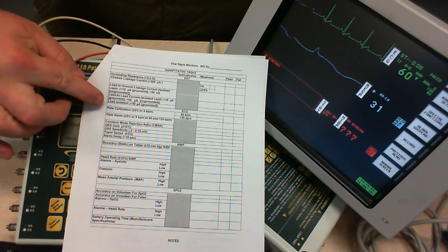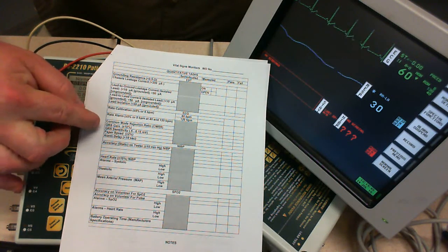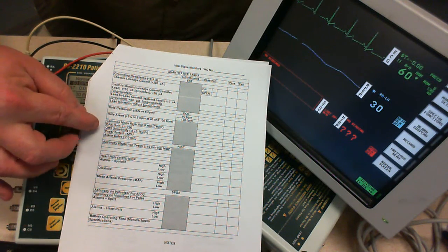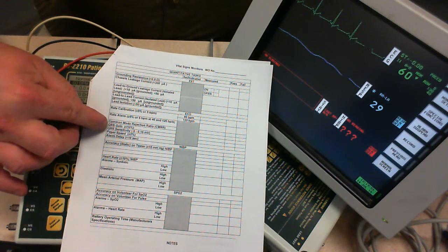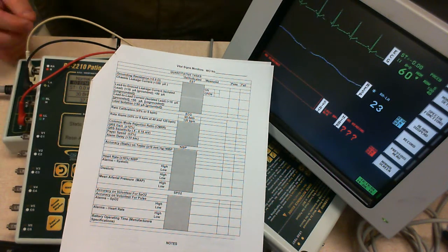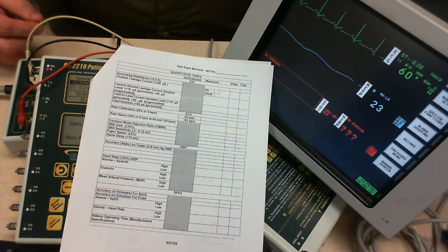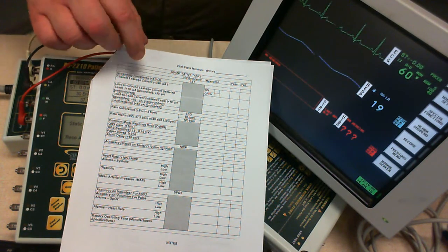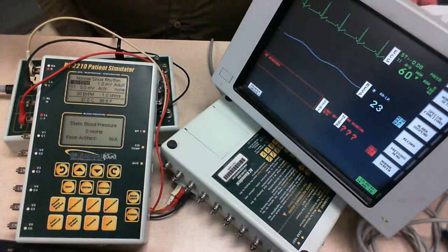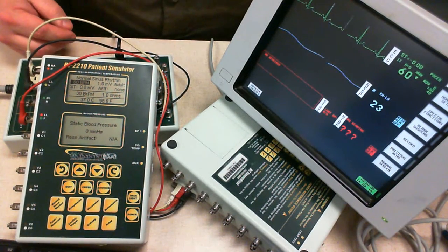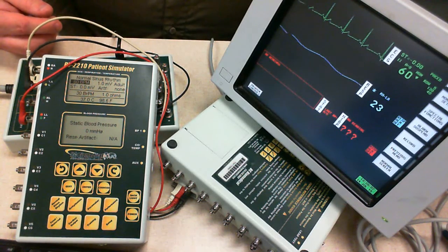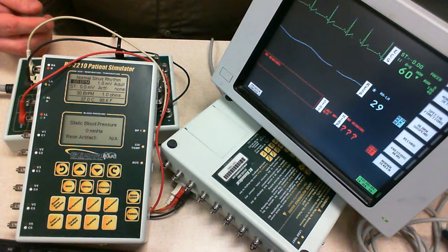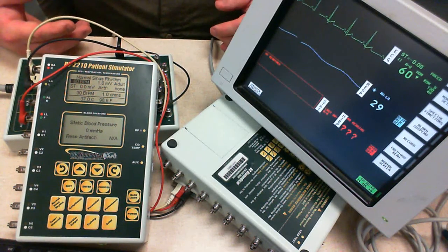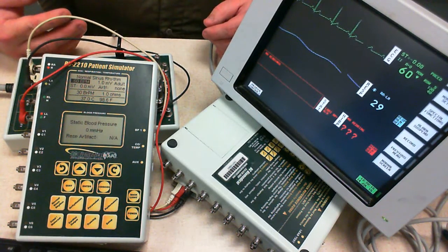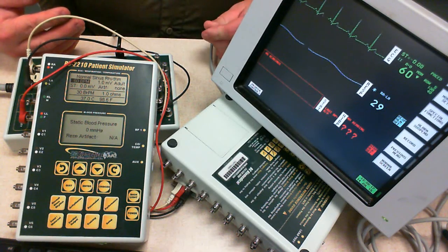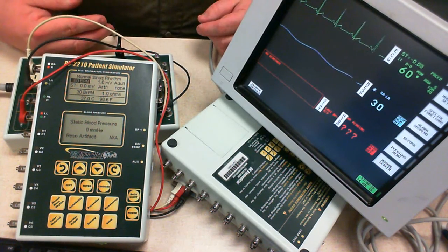Something that starts with rate calibration, rate alarm, then goes through common mode rejection ratio, the gain sensitivity, paper speed, and alarm delay. And those are the tests that we're actually going to do in this lab. So I'm going to put this sheet off the side so that I cover those in that order. And hopefully you all can follow along. I've got the monitor tilted here so that I can hopefully show you how to activate the controls as necessary. They're actually pretty straightforward. Everything should work as you're used to.